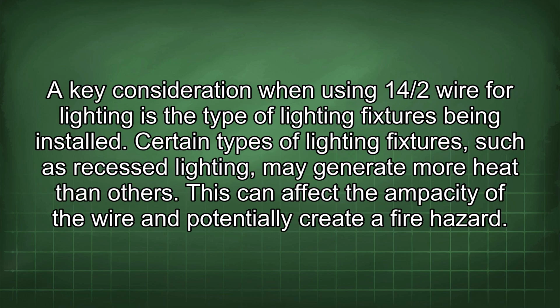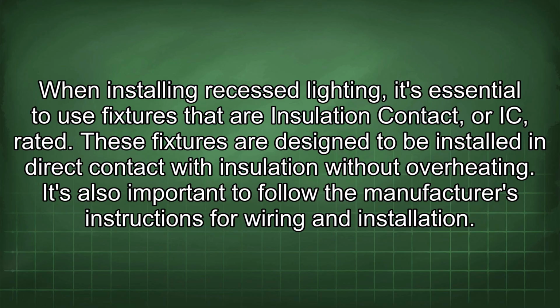A key consideration when using 14/2 wire for lighting is the type of lighting fixtures being installed. Certain types of lighting fixtures, such as recessed lighting, may generate more heat than others. This can affect the ampacity of the wire and potentially create a fire hazard. When installing recessed lighting, it's essential to use fixtures that are insulation contact, or IC, rated. These fixtures are designed to be installed in direct contact with insulation without overheating. It's also important to follow the manufacturer's instructions for wiring and installation.